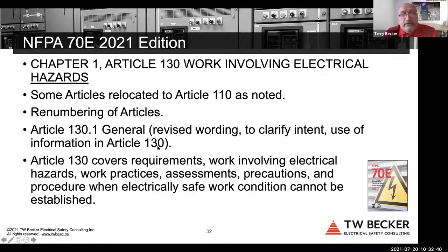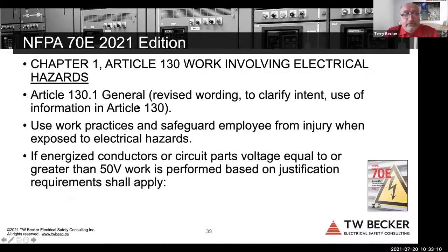So Article 130, again, moving content to Article 110, the same thing for Z462, but some introductory text was added because a whole bunch of information disappeared and there was a gap. So what was added was language to introduce Article 130, and the same thing for Clause 4.3 in Z462, right? So some general introductory language, because we took a whole bunch of stuff and moved it from Article 130 to 110, or from Clause 4.3 to Clause 4.1. All right, so revise the wording, clarify intent, use of Article 130, right? So work practice and safeguarding employees when we can't establish an electrically safe work condition.